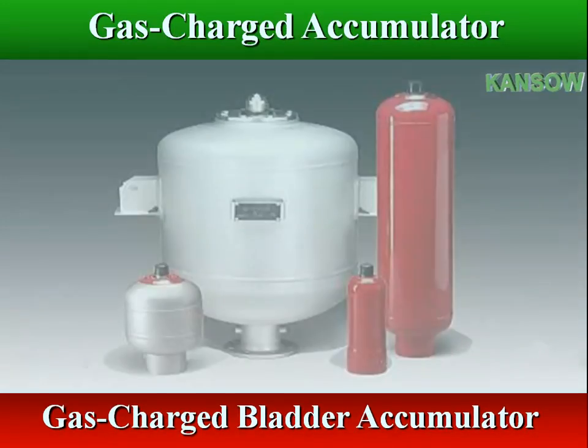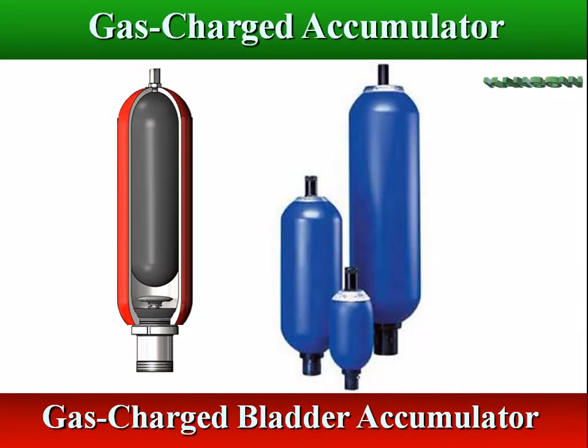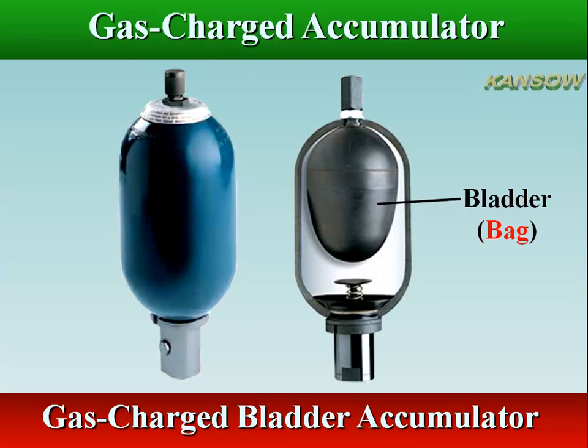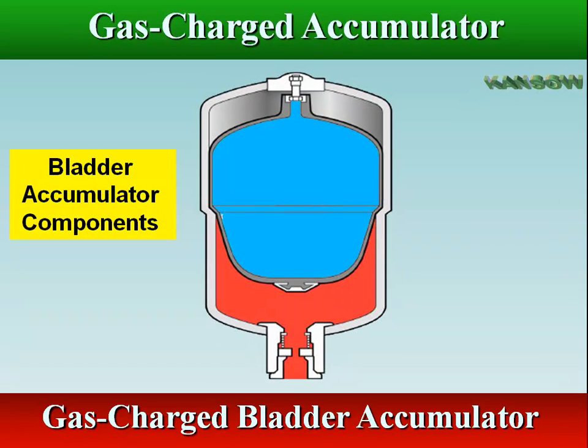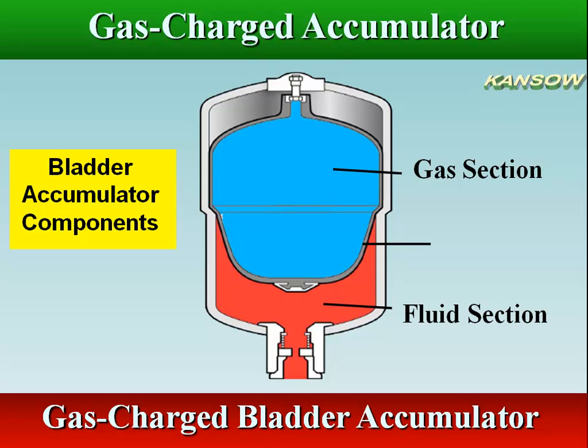A bladder accumulator consists of a seamless high-pressure cylinder with an internal elastomeric bladder, with pressurized nitrogen on the inside and hydraulic fluid on the other external side. A hydraulic bladder accumulator consists of a gas section inside the bladder and a fluid section outside of the bladder. The flexible rubber bladder acts as a gas-proof barrier.